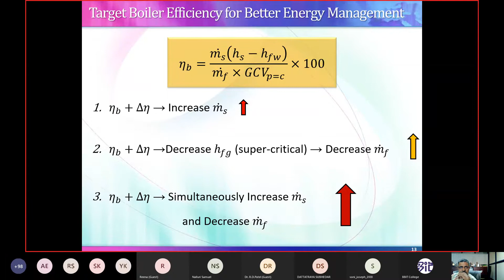Another way of looking at boiler efficiency. We are firing the fuel into the furnace. Once we fire it, it has its own efficiency, which I call the combustion efficiency. This will generate hot flue gas. The hot flue gas will transfer energy to the water finally. So your overall efficiency is eta combustion times eta HT. If we can individually improve eta combustion and eta heat transfer, we can improve the boiler efficiency.